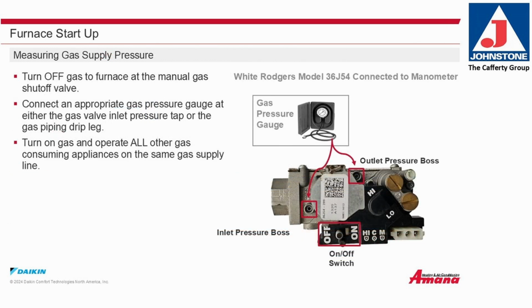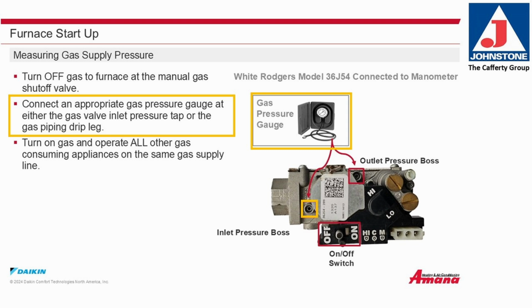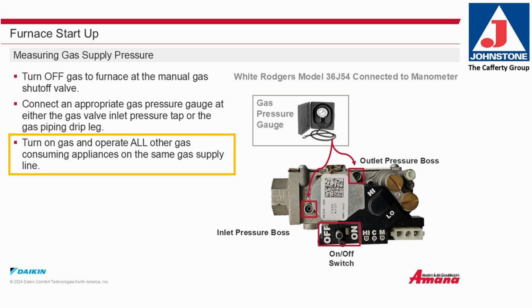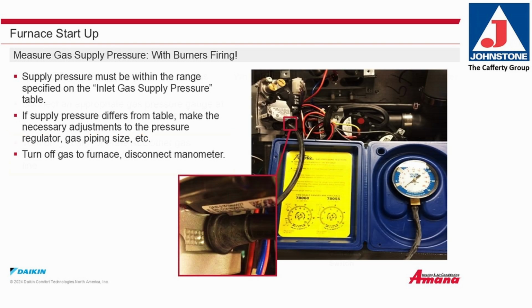Measuring gas supply pressure. Turn off the gas to the furnace at the gas shutoff valve. Connect an appropriate gas pressure gauge at either the gas valve inlet pressure tap or the gas pipe drip leg. Turn on the gas and operate all the other gas-consuming appliances on the same gas supply line. Measure the gas supply pressure with the burners firing. Supply pressure must be within the range specified on the inlet gas supply pressure table. If supply pressure differs from the table, make the necessary adjustments to the pressure regulator, gas piping size, etc. Turn off the gas furnace, disconnect the manometer.